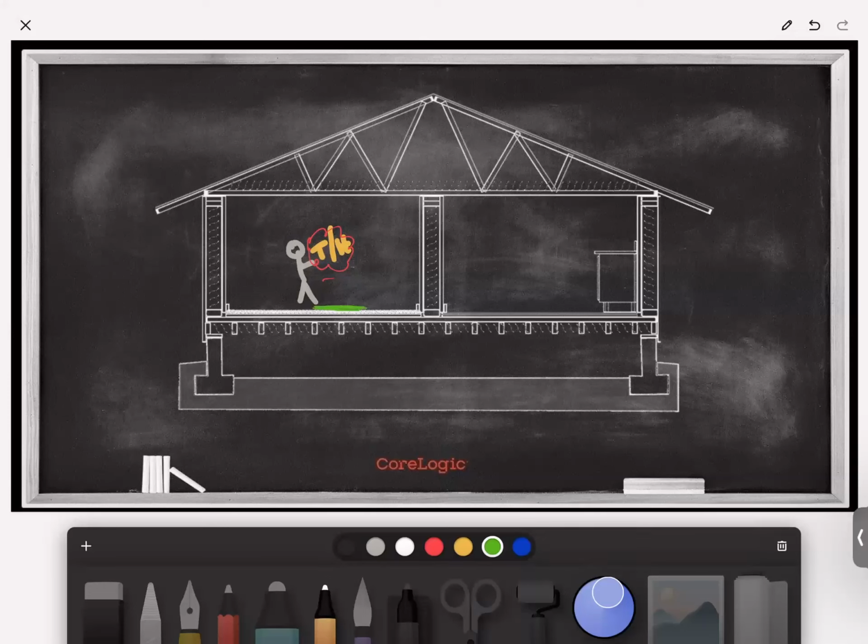If what I'm trying to dry is that floor, or it's the psychrometry in here. If what I'm trying to dry are the surfaces inside that wall assembly, that's where the psychrometry matters, right? It's the air that is in contact with the wet surface that's doing the work. It's not the air in the middle of the room.